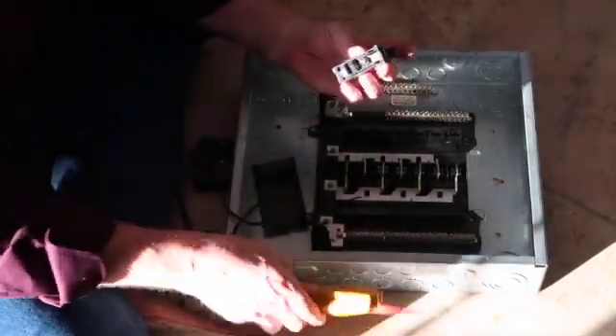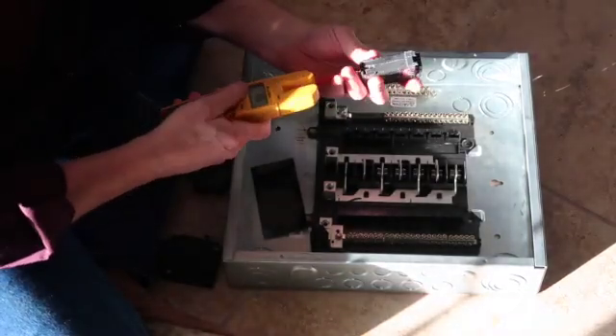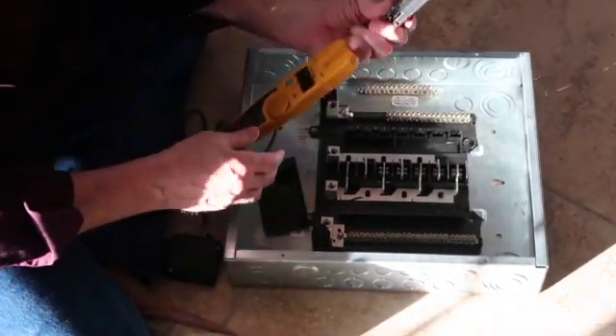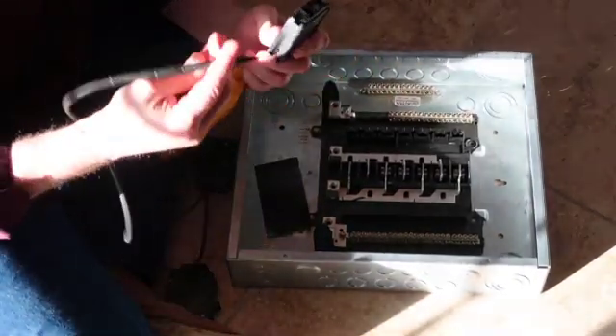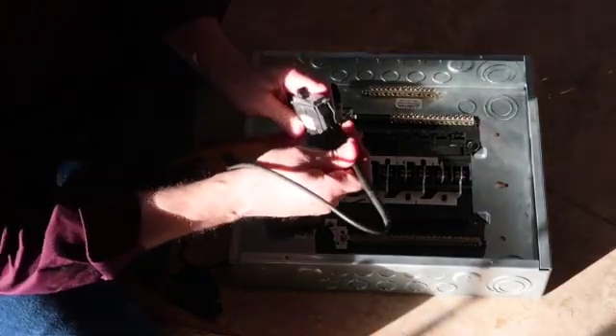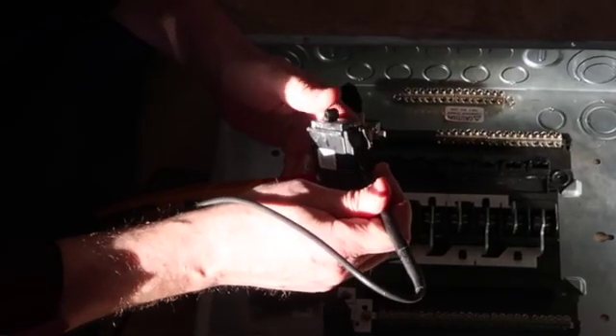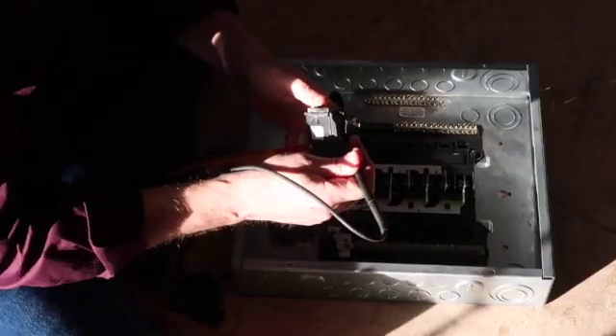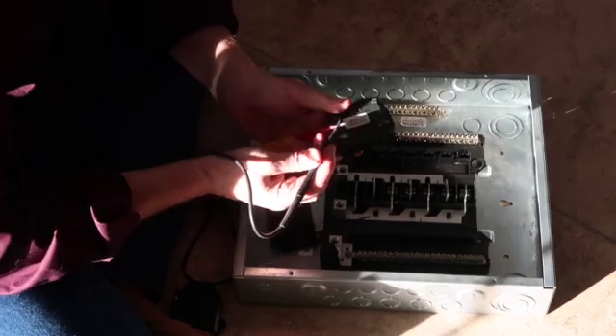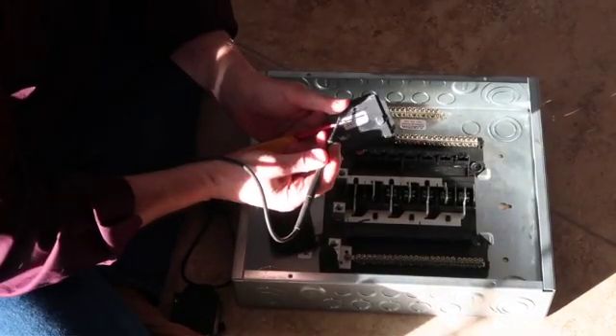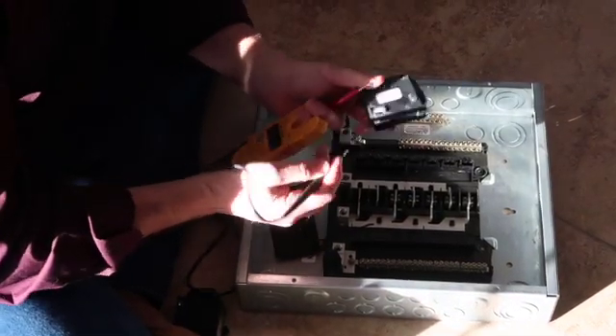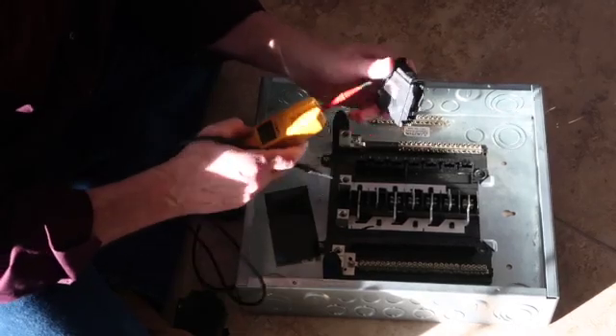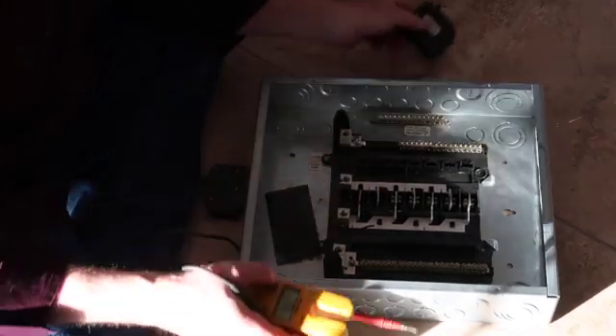It was stabbed in. Maybe this breaker doesn't work. So if you wanted to check a breaker, you would put your meter here. And then you would go ahead and put your meter over here where the outgoing wire goes to protect the circuit. And guess what? This breaker is no good. See, I get no continuity. If I go this way it beeps. I can hear it beep. It's pretty quiet but I can hear it beep.